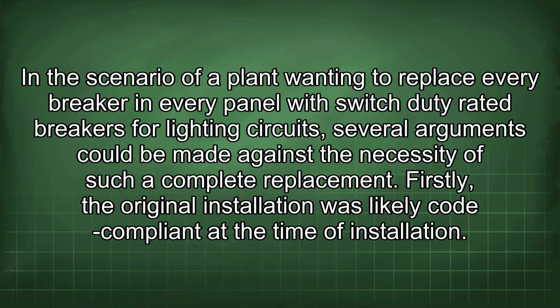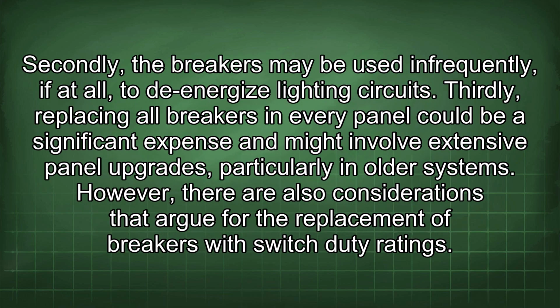In the scenario of a plant wanting to replace every breaker in every panel with switch duty rated breakers for lighting circuits, several arguments could be made against the necessity of such a complete replacement. Firstly, the original installation was likely code compliant at the time of installation. Secondly, the breakers may be used infrequently, if at all, to de-energize lighting circuits. Thirdly, replacing all breakers in every panel could be a significant expense and might involve extensive panel upgrades, particularly in older systems.